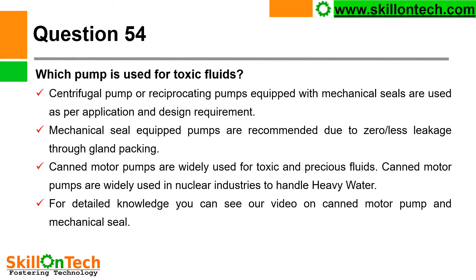Question 54: Which pump is used for toxic fluids? Centrifugal or reciprocating pumps equipped with mechanical seals are used as per application and design requirement for toxic or precious fluids. Mechanical seal-equipped pumps are recommended due to zero or minimal leakage through gland packing. Canned motor pumps are widely used for toxic and precious fluids, including in nuclear industries to handle heavy water. For detailed knowledge, you can see our videos on canned motor pump and mechanical seals.